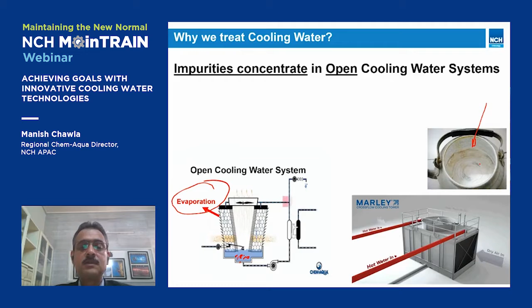Now, with more impurities because of concentration, we might have more problems. So, what do we do? We give some blowdown. We take some part of this concentrated water and throw it out. But as the water evaporates, some water is lost because of that, and some part of water is lost because of the blowdown, so the level in the cooling tower will tend to fall. So, what do we do? We put less concentrated makeup water back in the cooling tower. Now, this whole process of concentration, we sometimes use the term cycles of concentration, right?